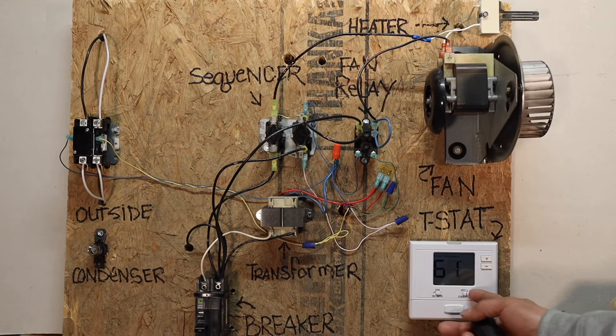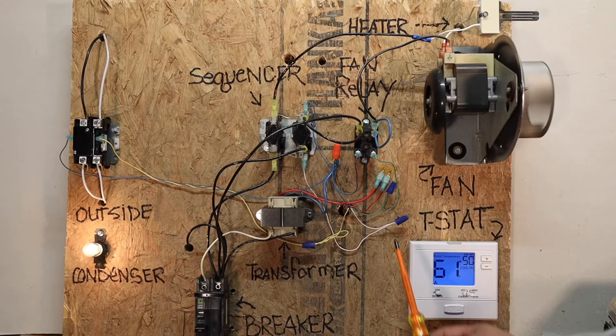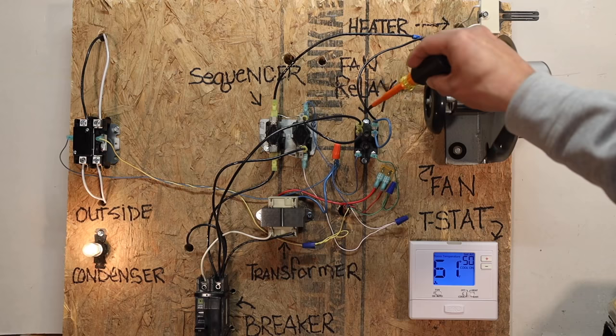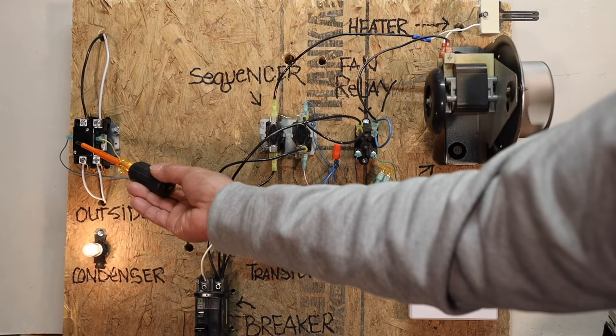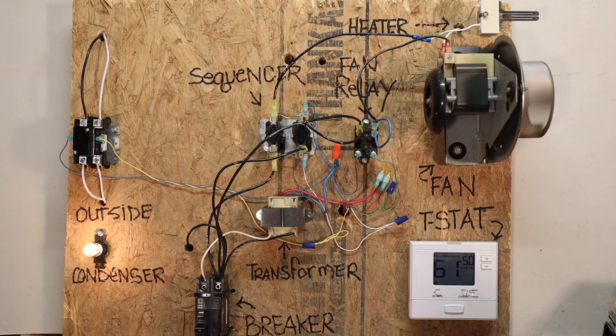Let's do that. So right now you're getting your 24 volts going to the fan relay. It's making a circuit at the normally open end, turning on your blower. You're also getting 24 volts being distributed outside to your contactor, which is turning on your outside unit. Thus you have air conditioning. I'm going to turn that off.